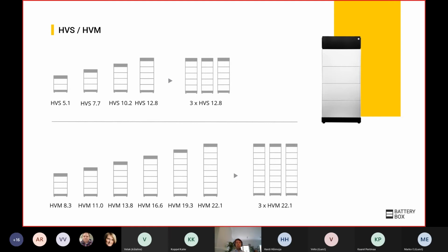For the high voltage medium, these are 50 volt, 50 amp hour modules. You can start with 3 of them in series, giving 150 volts and 8.3 kilowatt hours of capacity, and have up to 8 in series, reaching 22.1 kilowatt hours at about 400 volts system voltage. Same as with the HVS, you can have up to 3 towers in parallel.